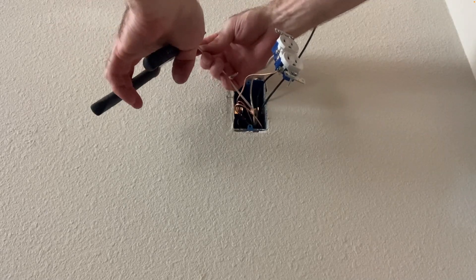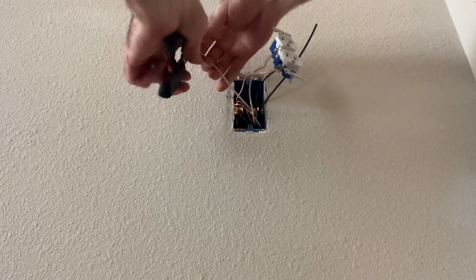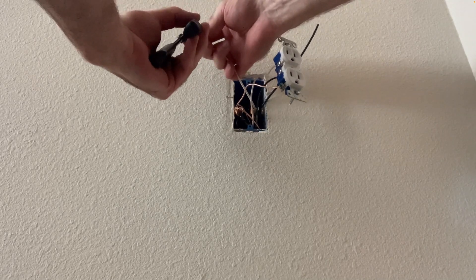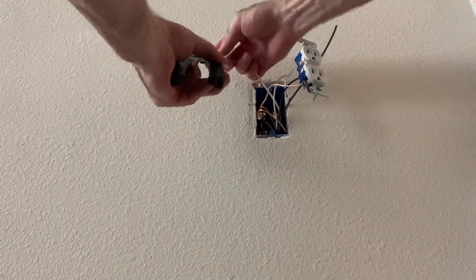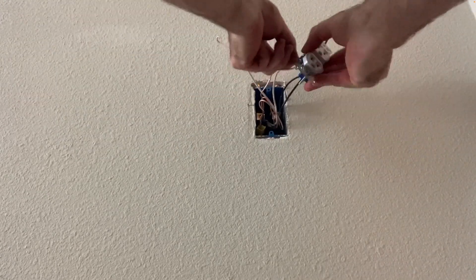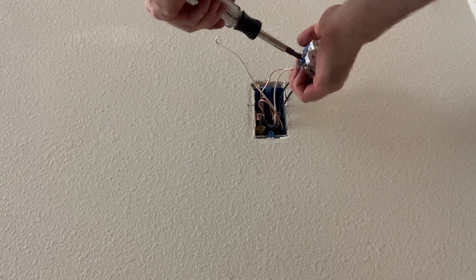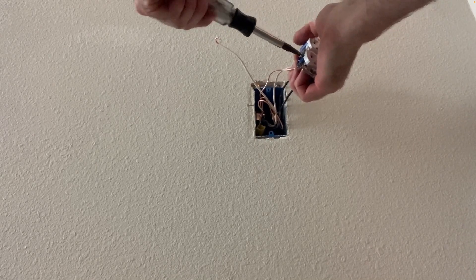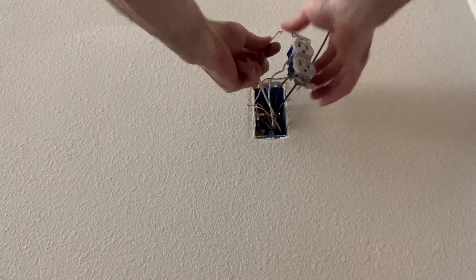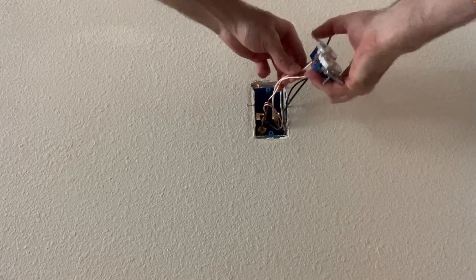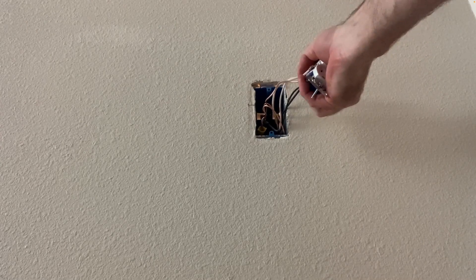We'll prep our neutral wire and our hot black wire. Now, these outlets have backstab connections—I don't recommend using those. I recommend using the screw terminals. It's a much more solid connection. The screw terminals are safer than just doing the backstab. That's why you'll note here I'm using the screw terminals.